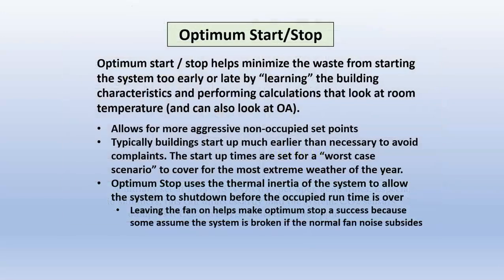Optimum start and stop, we discussed briefly before. It allows you to be more aggressive with your non-occupied set points, because now you know the BAS is going to handle it. If you get a cold snap or something weird, it's going to deal with it. This stops people from running their system a lot more than they need to. And as I said about optimum start, you need to let people know that it's coming. But sometimes, as a bridge gap or just a compromise, you can still do optimum stop, just leave the fan running. And then they won't even know that the HVAC is off.